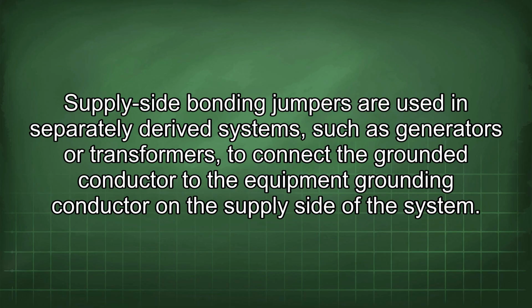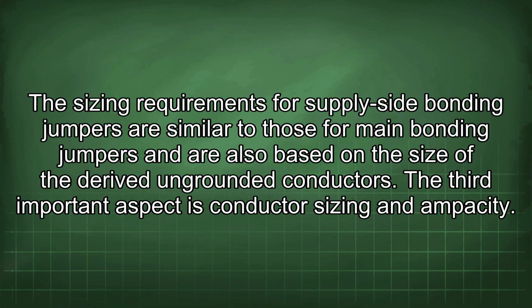Supply-side bonding jumpers are used in separately derived systems, such as generators or transformers, to connect the grounded conductor to the equipment grounding conductor on the supply side of the system. The sizing requirements for supply-side bonding jumpers are similar to those for main bonding jumpers and are also based on the size of the derived ungrounded conductors.